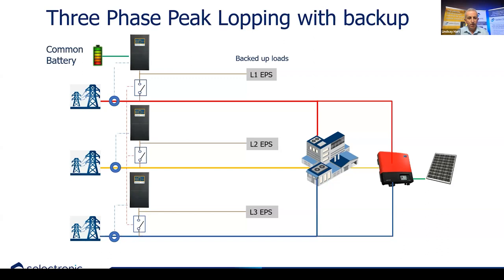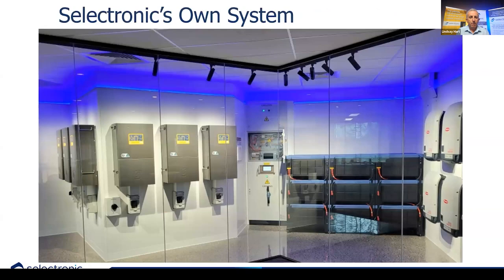Here's a little example of what we've done at our own factory. We have six 20-kilowatt inverters, so we've got 120 kilowatts of battery power, along with 240 kilowatt-hours of SelectCell lithium batteries, and about 80 kilowatts of Fronius inverters with 100 kilowatts of PV. And this is allowing us to make sure we don't have to upgrade that grid supply.